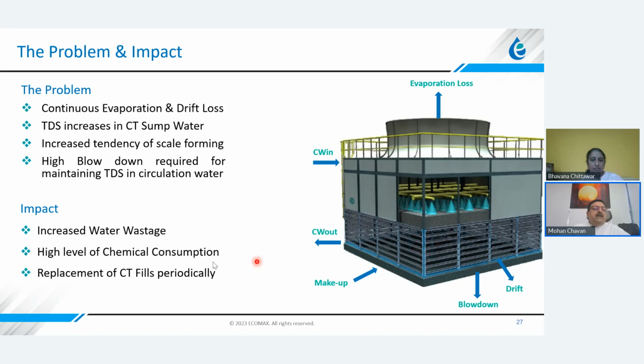towers. So the impact of all this is mainly increased water wastage, which we cannot avoid. High level of chemical consumption, because this water needs to be treated by chemicals. Replacement of fills periodically. So fills replacement cost is there every, let's say, 2, 3 years, 4 years, depends on the water quality.